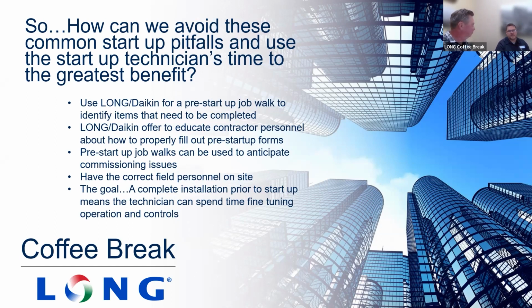That's more time, because now we have to wait for the filters to get on site, and it creates a delay. It can cause some premature faults and alarms in the machine. Once again, if the filters are extremely plugged because there's drywall dust, we could get intermittent high limit trips on a furnace. If we're trying to run that unit in a temporary capacity to heat a gym so they can put the floor in, it's hard to keep it heating if it can't move air. Right. So those conditions of starting it early create maintenance concerns with the unit that don't always get addressed when we're doing a temporary startup.